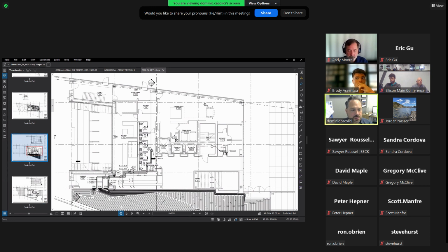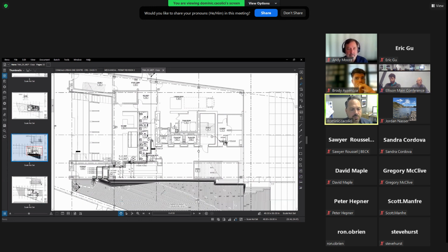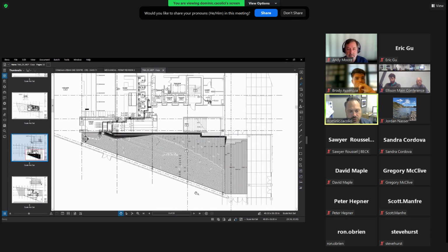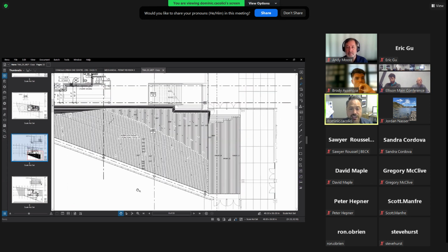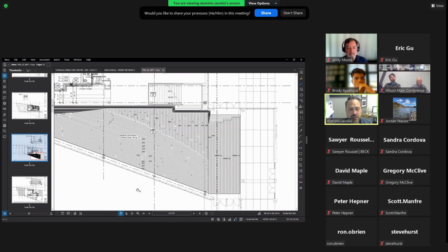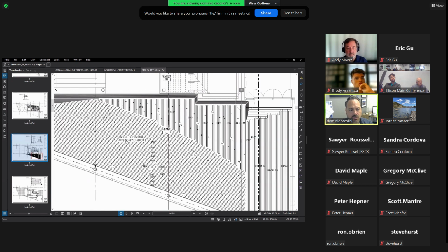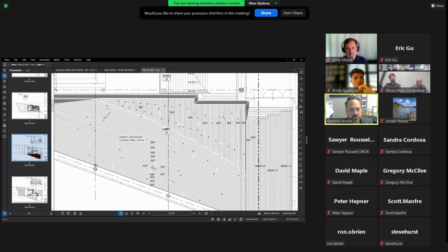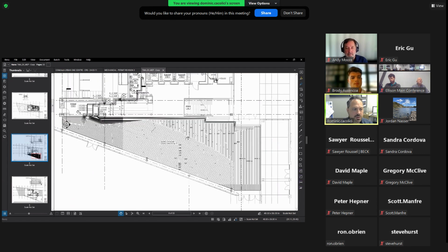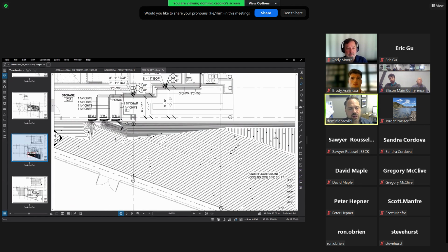From a piping scheme, the radiant floor has been laid out, and I'll say laid out multiple times with the manufacturers. Watts Radiant and Uponor are familiar with this, they laid it out, but you have to be mindful of the maximum lengths of piping. So the way it's circuited is pretty important, as is where it comes back to the manifolds.